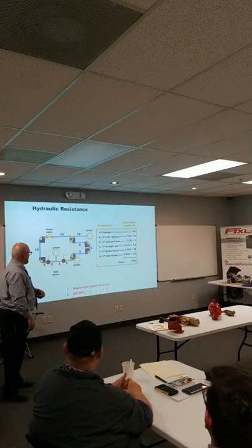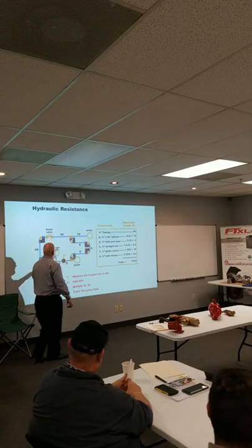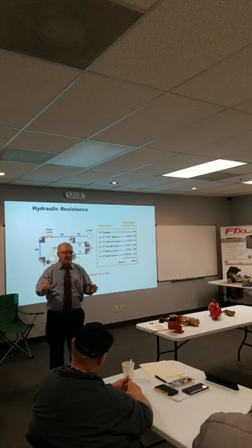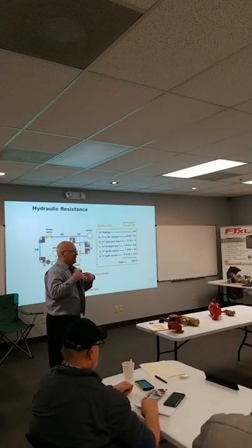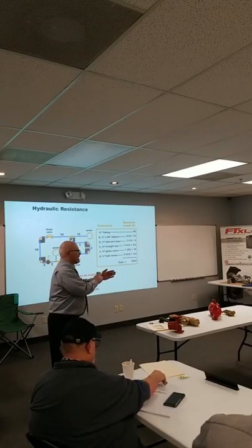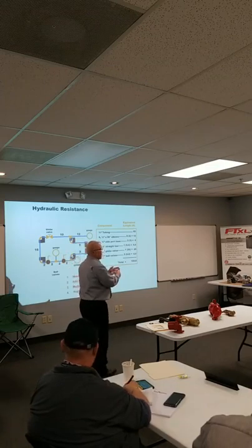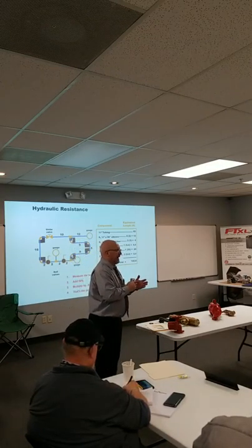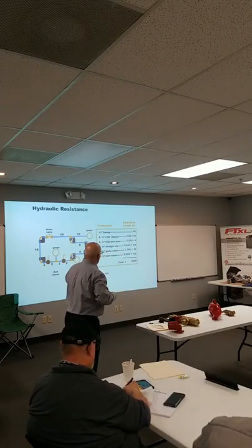You're creating resistance. So as a rule of thumb, very simple: if you measure the longest loop in run, if I have three zones, one's 50 feet, one's 75 feet, and one's 100 feet, and I have to have a pump to overcome resistance, do I add all those resistances? The answer is no. I have to just overcome the most resistant loop in the system. If I have enough pump head to do that, then I can get the flow I need. So I size it for that 100-foot loop.